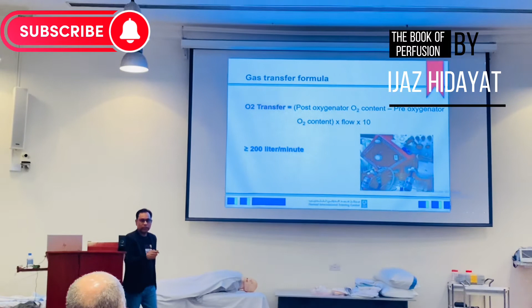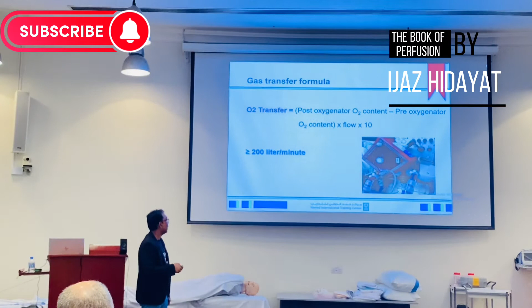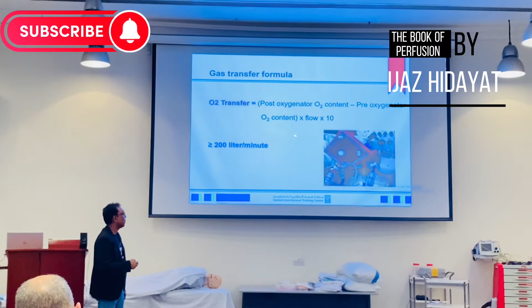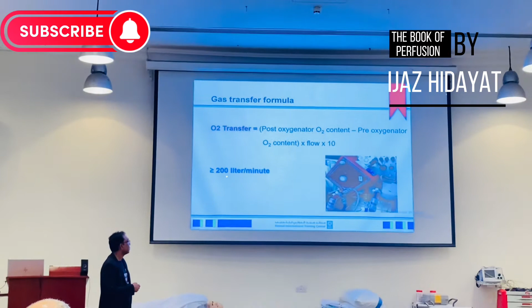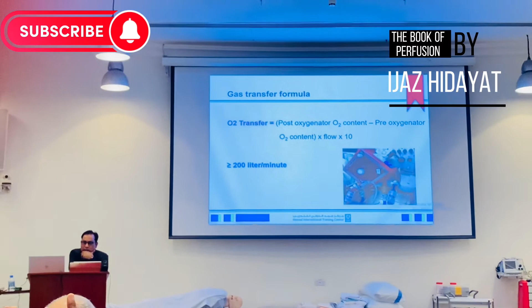So normally we are using the Maquet oxygenator, and we can use different oxygenators. But for the Maquet, we have the flow chart with us. This formula is for all oxygenators: post-oxygenator content minus pre-oxygenator content, times the pump flow, times 10. This is the fixed formula. If your result is 200 and above, we are okay with the same flow. If it is less, then we have to change the oxygenator.